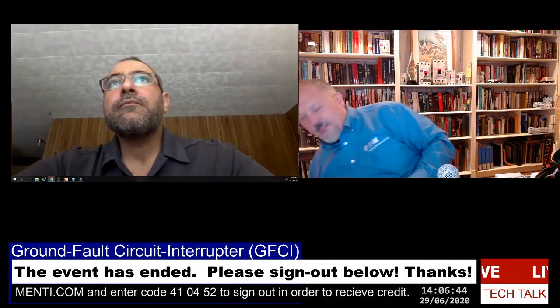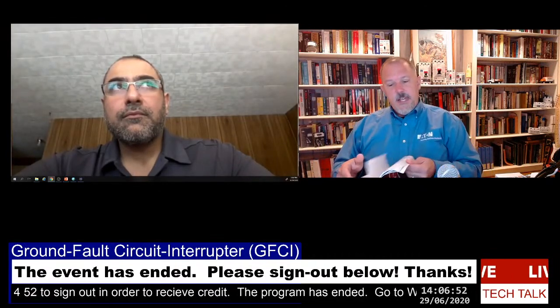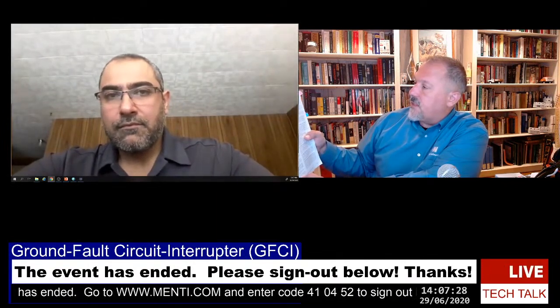So John Clements asked about insight on 210.8(A)(10). If I look at the code book in 210.8, we moved and expanded the GFCI requirements in dwelling units. We moved up to all branch circuits, any rating in those areas. So we still kept those rooms. We expanded in basements, not just unfinished basements. But if you look at 210.8(F), it says outdoor outlets, which is completely new. All outdoor outlets for dwellings other than those covered in 210.8(A)(3) exceptions supplied by a single phase branch circuit rated 150 volts to ground or less, 50 amps or less, shall have ground fault circuit protection for personnel.